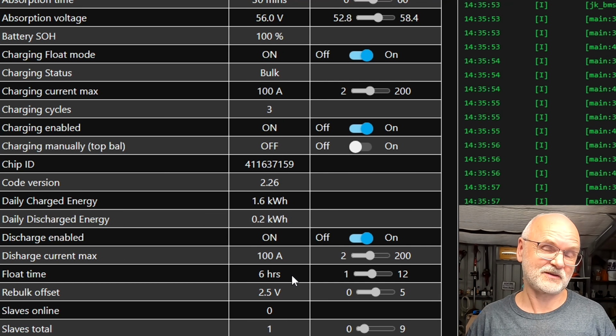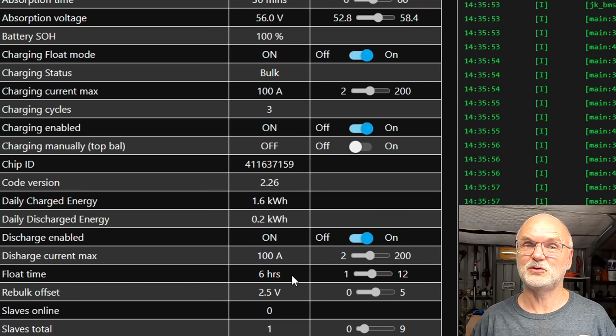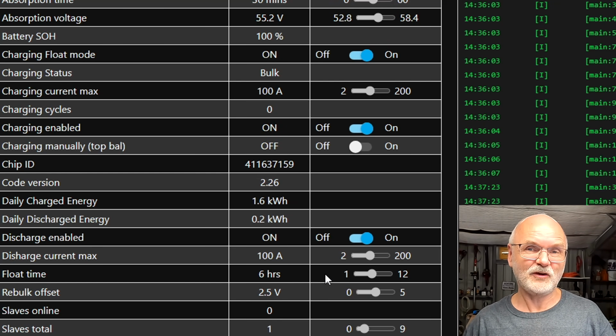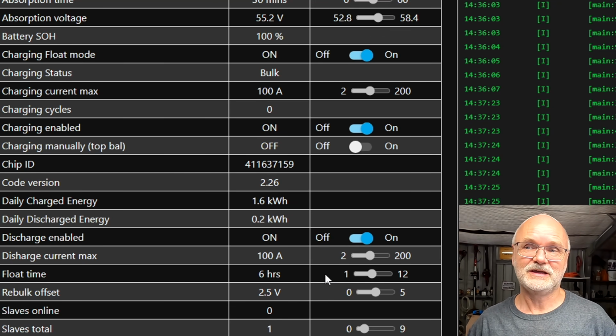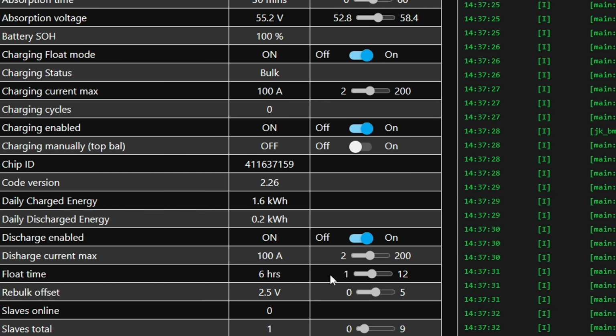If you have a Victron system, for example, your MPPT solar charge controllers or your Multiplus will do this automatically after the sun has set and there's no solar power coming in anymore. The Victron system realizes the day is over, and the next time there is solar power available, it starts a new cycle. We can simulate exactly this with the PIDA board, because whenever you hit your float voltage, you can set the timer for the float time according to your circumstances and to the design of your system.